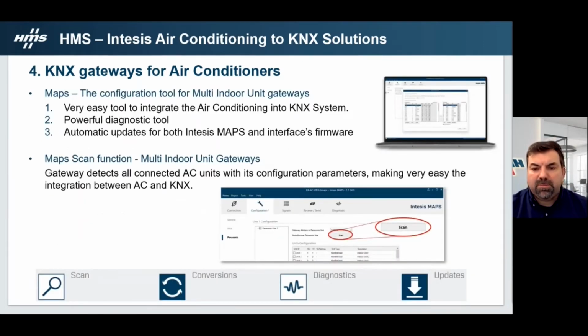As mentioned in the previous slide, we can count with the powerful configuration tool for our KNX indoor unit gateways. It is the maps. The maps is a very easy tool to integrate the air conditioning into the KNX systems. It works as a powerful diagnostic tool, and all updates, when released, are automatically available to be installed in the Intesis maps and Intesis gateways. This tool is developed to make our life easier. It has a scan function where it is just needed to click the scan button, this one that we can see in the slide, and after that, all connected AC units will be listed with the configuration they already have. And that's it. The air conditioning is configured to be integrated on the KNX system.